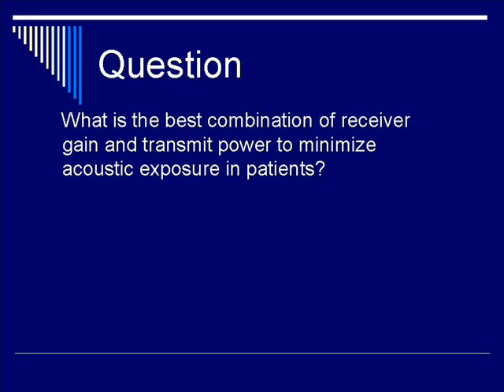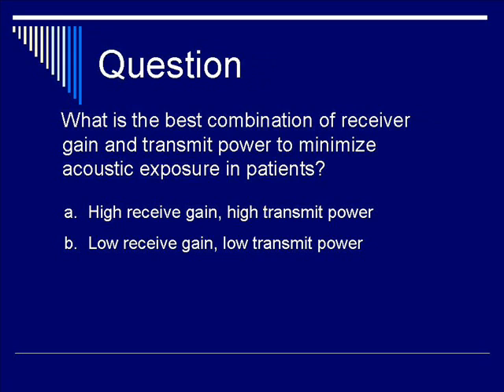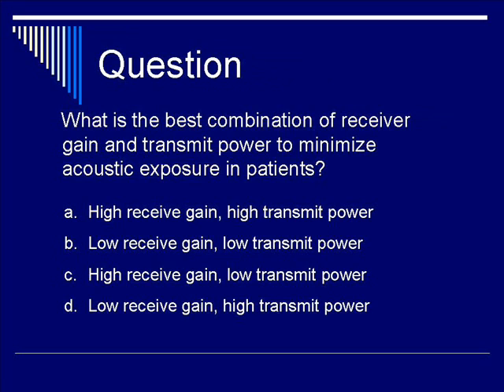Let's do a question. What is the best combination of receiver gain and transmit power to minimize acoustic exposure in patients? The four options are: A — high receiver gain, high transmit power; B — low receiver gain, low transmit power; C — high receive gain, low transmit power; or D — low receive gain, high transmit power. The correct response is C, high receive gain with low transmit power. This combination optimizes the image while minimizing acoustic exposure for the patient.